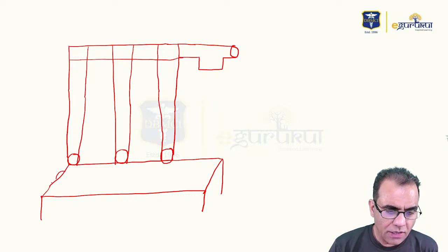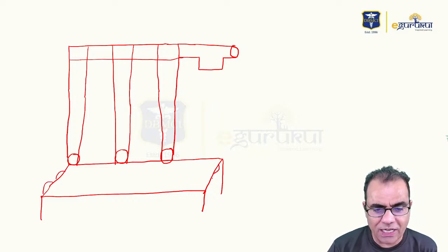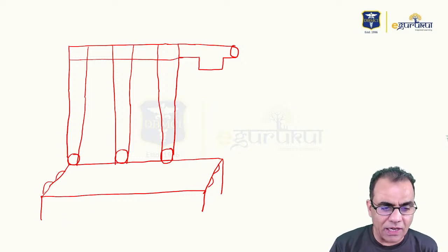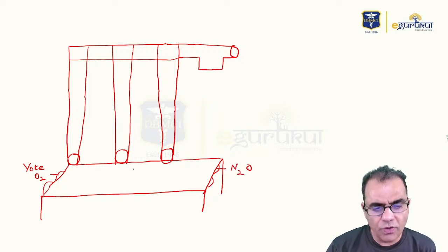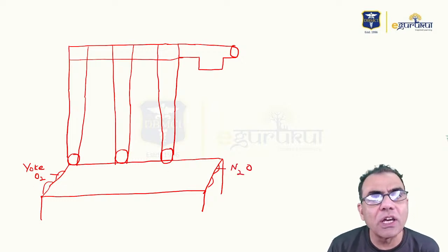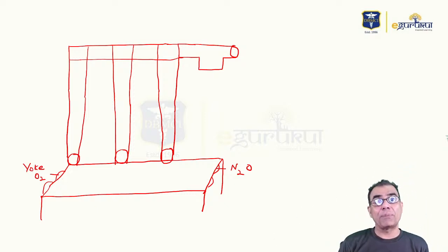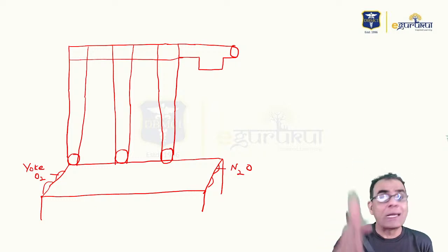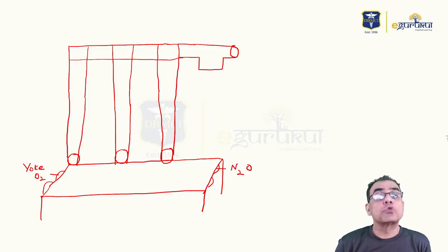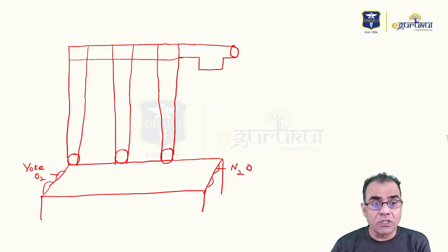So this is the portion where cylinders or central supply are going to be attached. And the portion where central supply or cylinder is going to be attached, I told you, is called the yoke. Now say this is the yoke for oxygen and this is the yoke for nitrous oxide. So obviously the oxygen cylinder or central supply will be attached here. But the pressure in cylinders and central supply is very high: 2000 pounds per square inch in a cylinder and 60 pounds per square inch in central supply. That pressure is too high. 2000 can burst everything in this room.